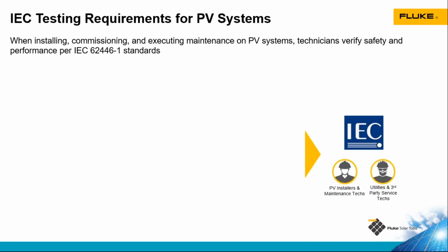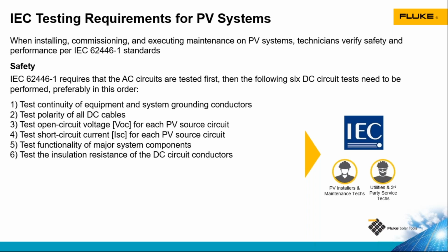In the United States, and I believe in Canada, it is not a legal requirement, but it's still a really good standard to follow to ensure that we're testing to make sure that the system is going to be safe and operate properly. In this standard, there are two main categories of tests. The first one, category 1 tests, are for safety. So this starts off with testing the continuity of the bonding conductors, making sure all of our non-current carrying metal parts are electrically connected together, like our modules are connected to the racking, which is connected to the conduit, connected to the equipment grounding conductor, all the way through, that there's a low resistance connection there.